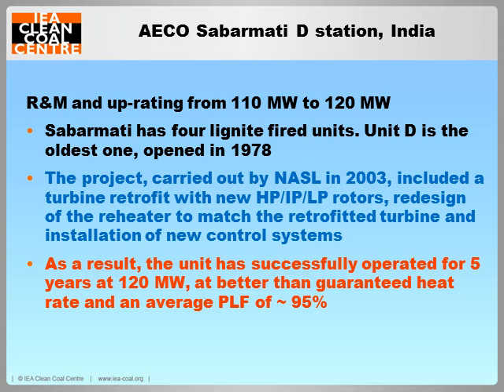This is another plant in India — actually a lignite plant, dating from 1978. Again, NASL carried out the retrofit project, including an uprating from 110 to 120 megawatts. Sabarmati has four lignite units; Unit D is the oldest, opened in 1978. The project carried out in 2003 included a turbine retrofit with new high-pressure, intermediate-pressure, and low-pressure rotors, redesign of the reheater to match the retrofitted turbine, and installation of new control systems. As a result, this unit has successfully operated for five years at 120 megawatts, at better than the guaranteed heat rate, and an average capacity factor of over 95%.